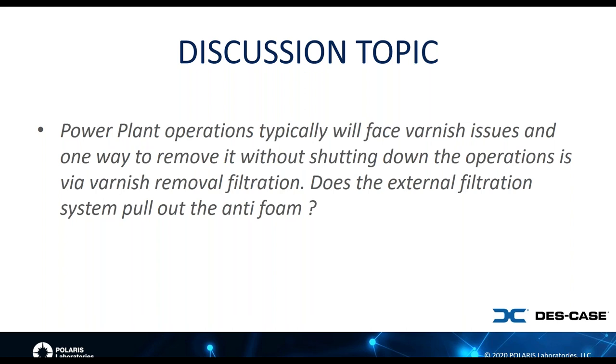When you say power plant, the assumption is we're talking about a turbine application, whether it's a steam turbine, a gas turbine, or combined cycle. If you talk about a gear oil or an engine oil, a common anti-foam additive we use there is methyl silicone. In the previous question, we talked about how that polymeric additive can be stripped using filtration. In low viscosity fluids like turbine oils and hydraulic fluids, the most commonly used anti-foam additive is a polymethacrylate, and polymethacrylates are truly dissolved within the oil.